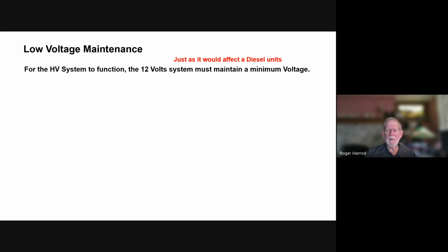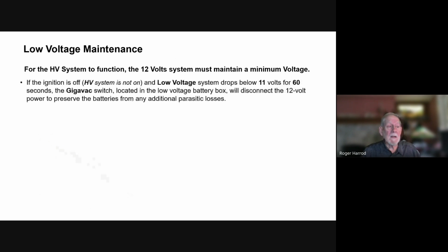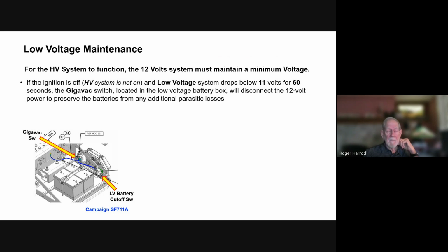Usually on the diesels, it's around 10.5 volts, and we'll have problems starting. The starter, the system just won't come up. Ours is around 11 volts for the Joule package. And unfortunately, on all these newer units today, with all the computers we've got on board, there are parasitic loads on these computers and on these battery packs, and it can drop below 11 volts. That's the point at which the unit won't start.